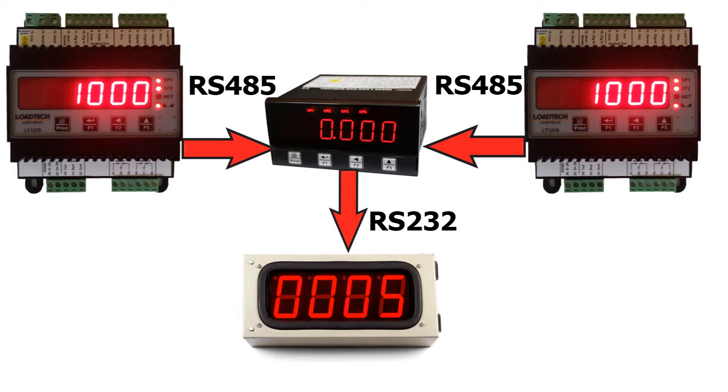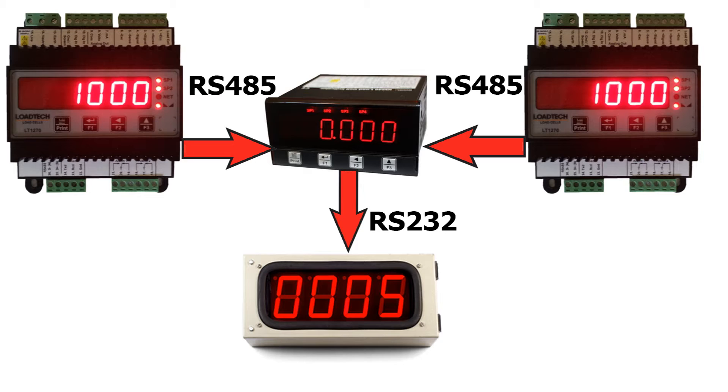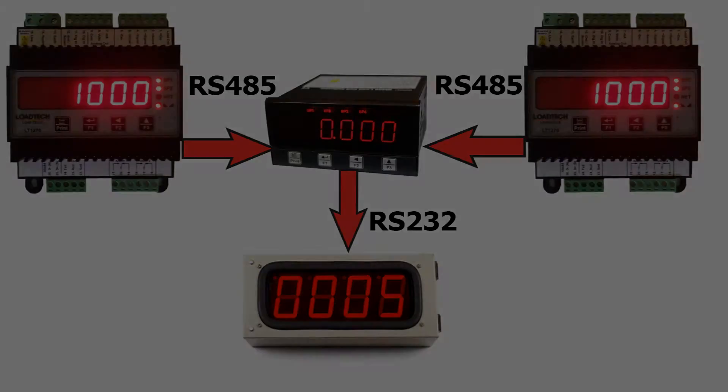Hello, today I'm going to explain how to set up a summation unit with two 1270 or 1240s and for them to work with a large display. The 1270 or 1240 is going to communicate using RS-485. The 1230 is going to be receiving data from the 1270 and 1240 via RS-485 and then sending it via RS-232 to the large display.